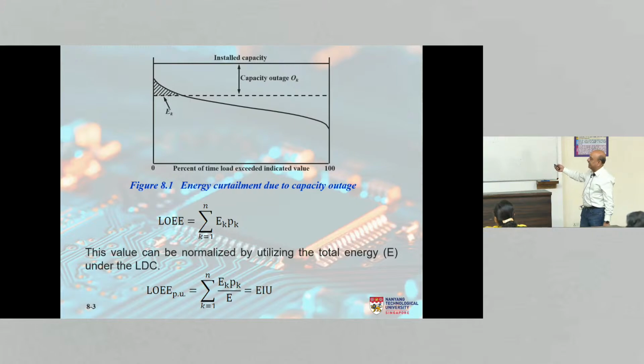So again, just to understand the concept, this is our installed capacity. This is the time, the load duration curve over 0 to 100% of the time, which could be daily, which could be monthly, which could be annual, doesn't matter. And if there is a capacity on outage, which may be O1, O2, O3, then you can see that we are not able to supply this much energy after that capacity outage takes place. So our objective will be to find this E subscript K, and we already know the probability of that happening because we know the probability of this capacity outage, right? So therefore our calculations will become quite simple.